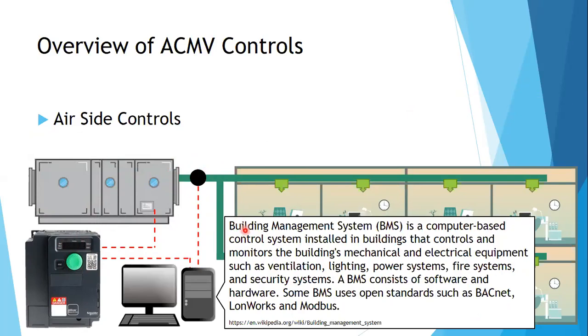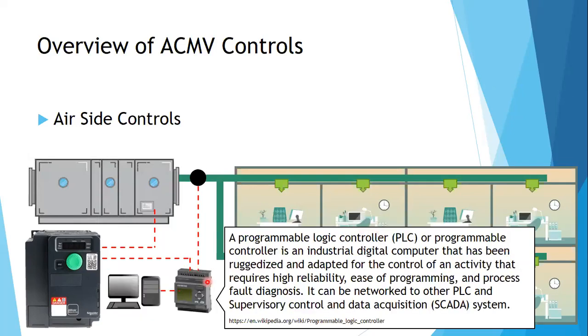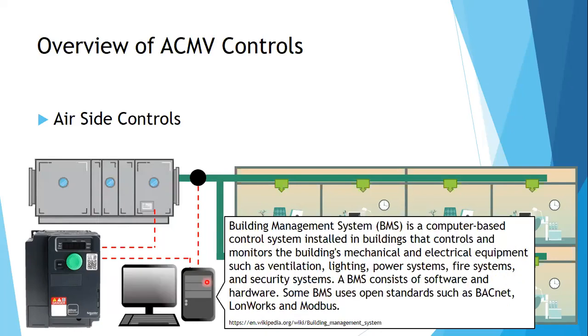There is also another one, building management system or building control system, automated control system, or sometimes it's called BMS. So BMS now, instead of having a rugged standalone mini computer, directly puts their signal into their system, and then they use control language. Standard control language such as BACnet, LonWorks, and Modbus. The signal goes to the DDC or digital controller and goes to the main server where the logic is stored. So now you only have one area where all these signals are coming from, and all the signals are going out to other equipment.